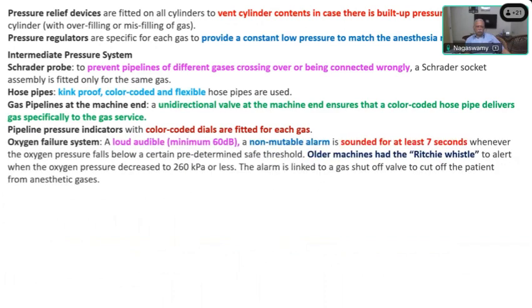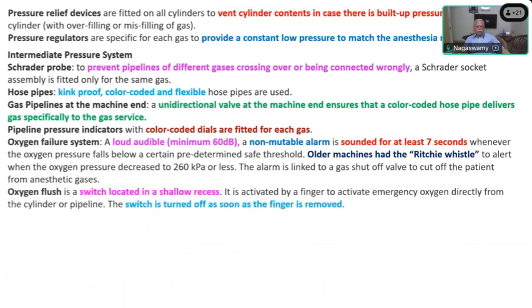And comes the oxygen failure system, which is a loud alarm to indicate that there is a fall in oxygen level, whereas older machines had what is called the Ritchie whistle to alert when the pressure drops. The oxygen flush is located in a shallow recess and is activated by finger, and it will return back to normal. In the earlier machine, it had a rotating type of button which could be pushed and then kept on for a long time without your finger being pressed. Whereas in the modern workstation, every time you want to activate it, you have to press it with your finger, and once you remove the finger, it automatically reverts back. That is a very important safety feature, because in the older machines it can be kept activated without your finger being on the button. That may result in barotrauma.